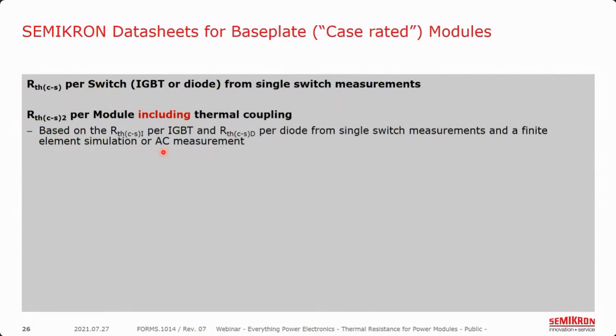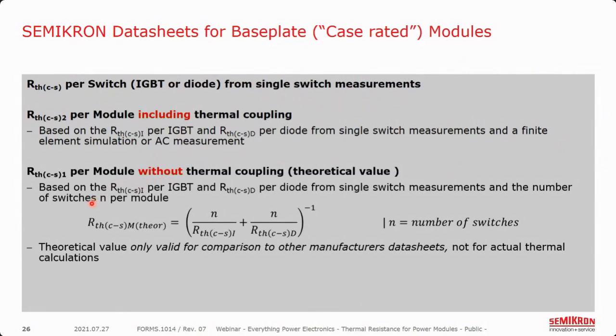Lastly, we've also provided in our data sheets the theoretically derived module-level thermal resistance that some other module manufacturers provide. This value is given so that R-module can easily be compared to another manufacturer's device — you can calculate it from the individual per-switch measurements as shown. But this R-theta case-to-sink subscript one value is only valid as a point of comparison between our data sheet and another manufacturer's data sheet, and really shouldn't be used for actual thermal calculations, because as we discussed, it's lower than any real thermal resistance you would measure.